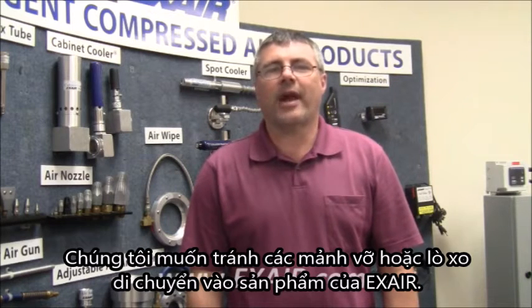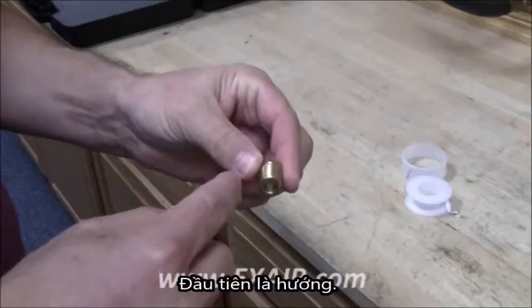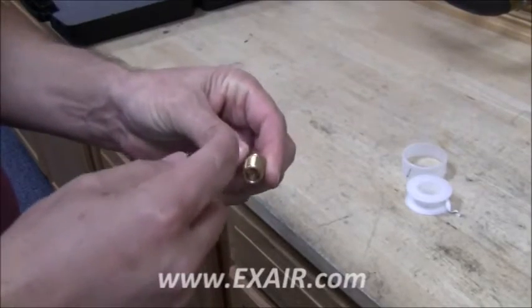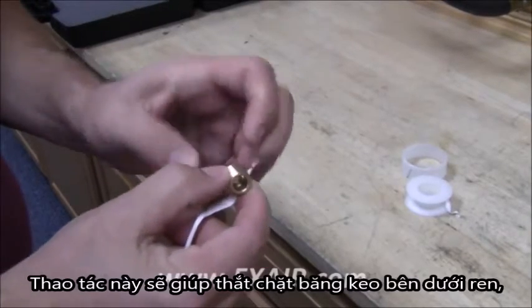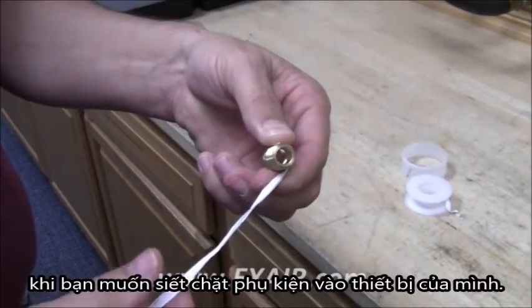We want to avoid having fragments or strings migrating into the EXAIR product. Two very important steps in using PTFE tape. First is the direction. You want to wrap it clockwise as you face the end of the part. This will help to tighten the tape onto the thread as you are tightening the fitting into your part.